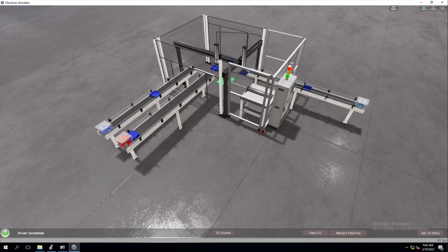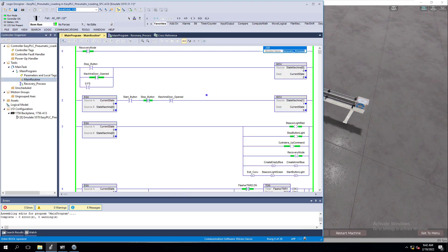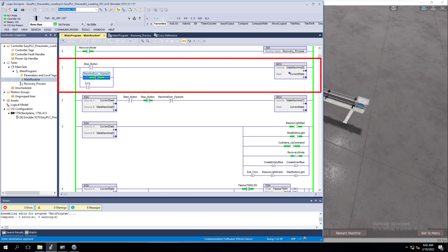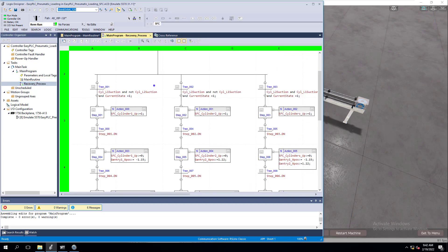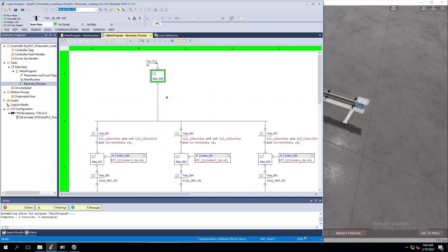So like in this case, if I just open the door like this, the machine stops and it's in a good safe state. Let's look at our ladder logic. Right here it shows the door is open. The state machine is in zero, so we're in a safe state. The machine is perfectly isolated. We're not doing anything with our recovery mode right yet, even though it is active.